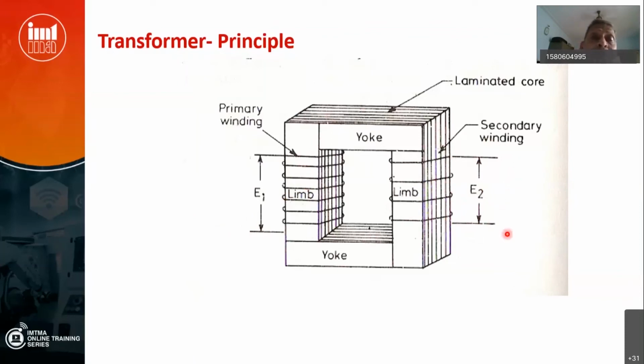So now you know the purpose of the transformer in a generating station: to step up the voltage to the level of transmission line voltage, so that line losses are reduced, current is reduced, conductor sizes are reduced, and transmission cost is reduced. In the receiving station, after receiving, you are stepping up or stepping down suitable to the user level. So for stepping up and stepping down, you require a transformer.